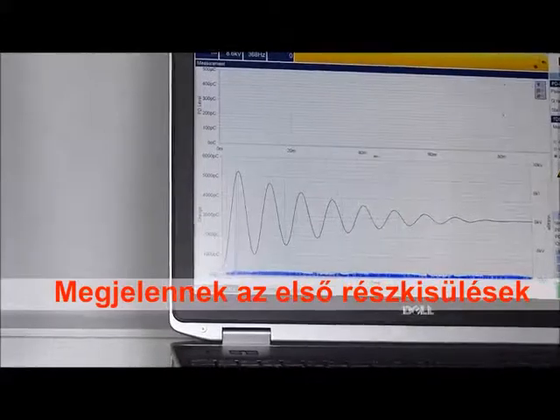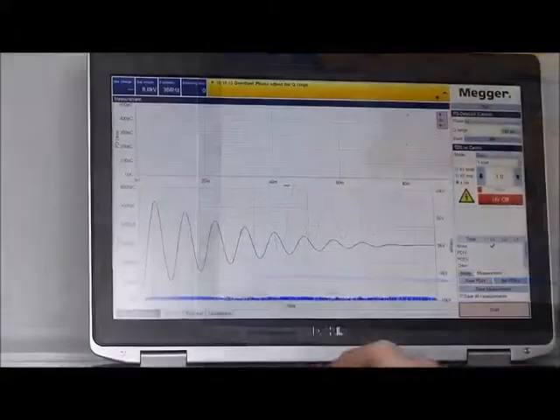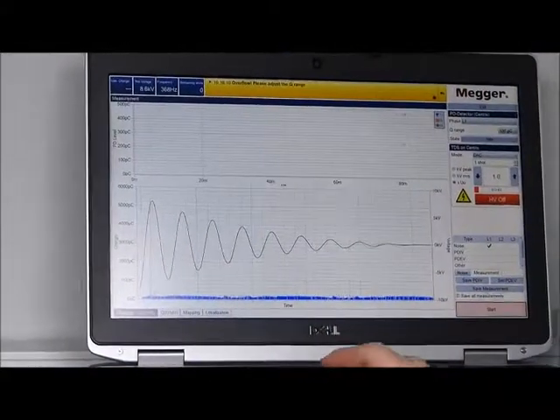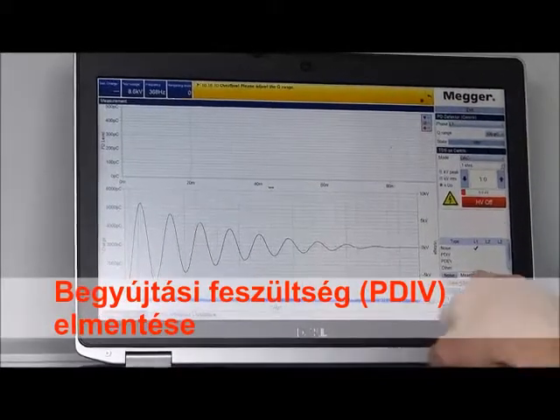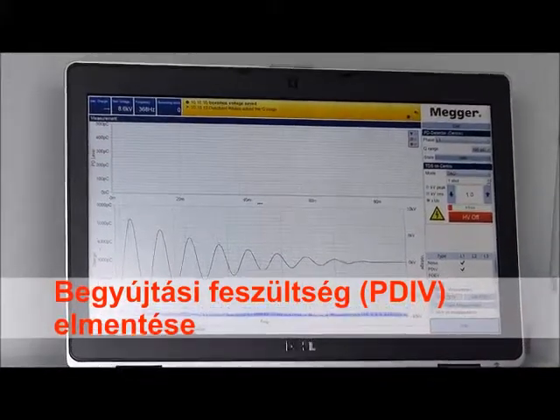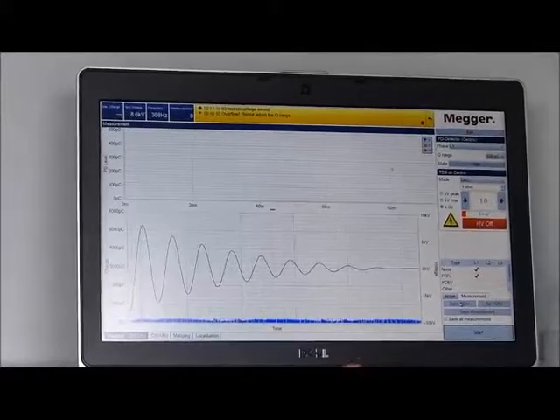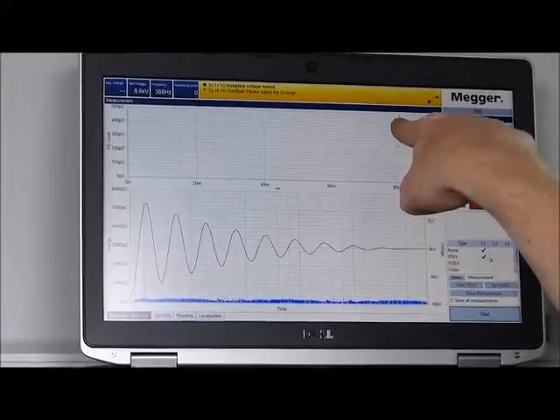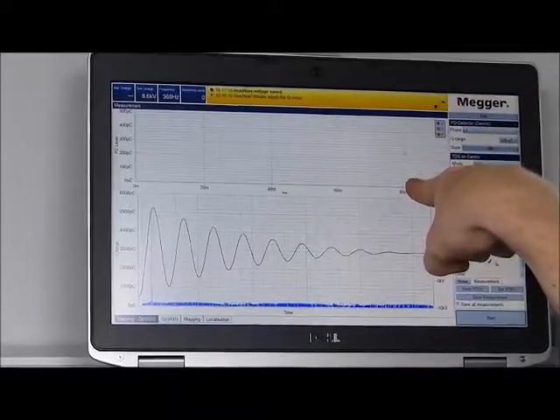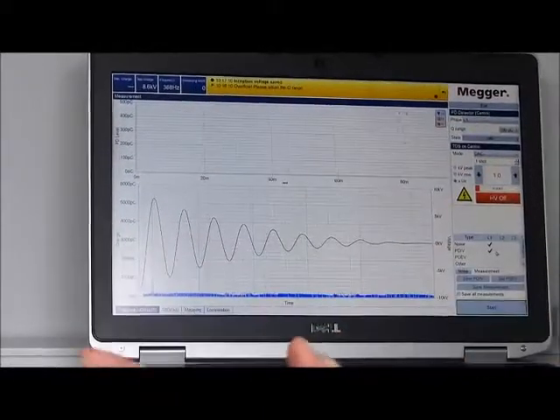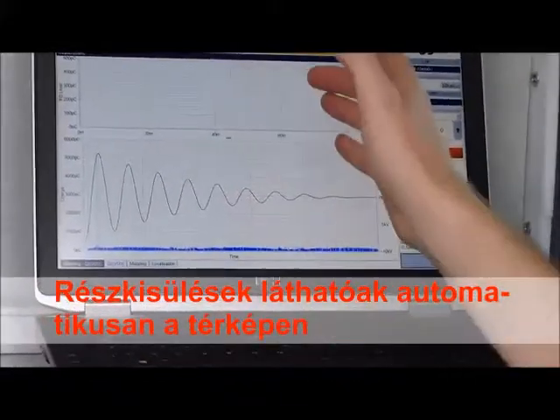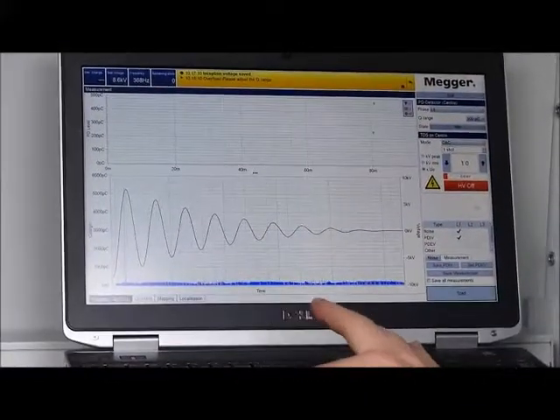So here we have the first partial discharges. And already, okay, so this is our partial discharge inception voltage. So we save it as PDIV. Done. And we already recognize here a few dots at round about 80 meters. So without doing anything, we already see, okay, most likely that could be our weak spot. So a few more shots.